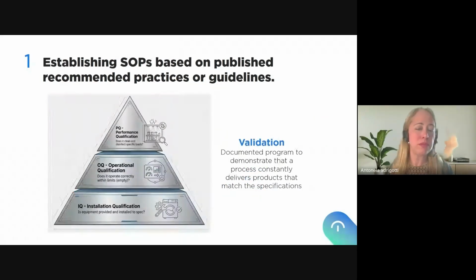But all of them coincide in terms of validation. When we are talking about washers, and this is also true for autoclaves or other types of sterilizers, but focusing on washing processes and thermal disinfection, we have to perform a validation. Validation is a documented program to demonstrate that the process consistently delivers products that match the specifications. The validation process has three steps: installation qualification, operational qualification, and performance qualification. The installation qualification asks, is the equipment provided and installed to specifications? Is the new equipment installed as it is supposed to be and working as expected?